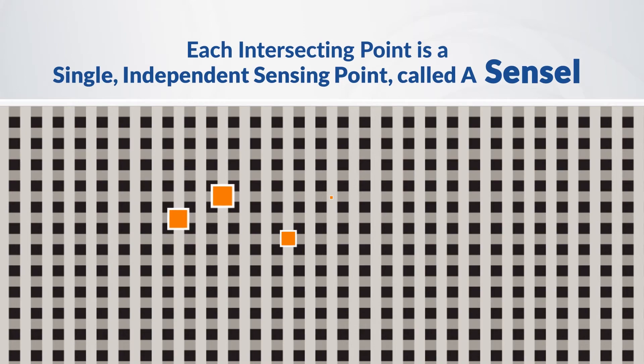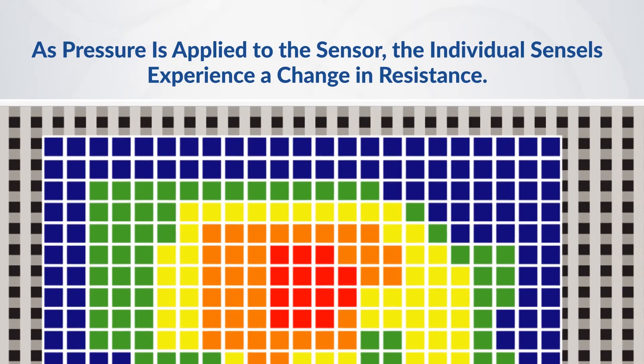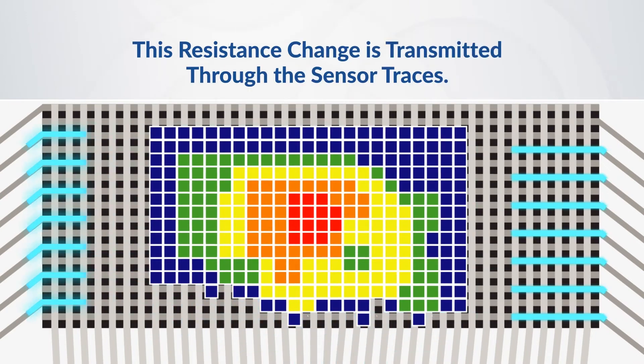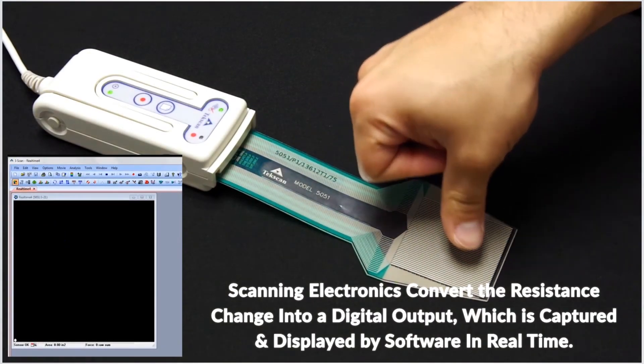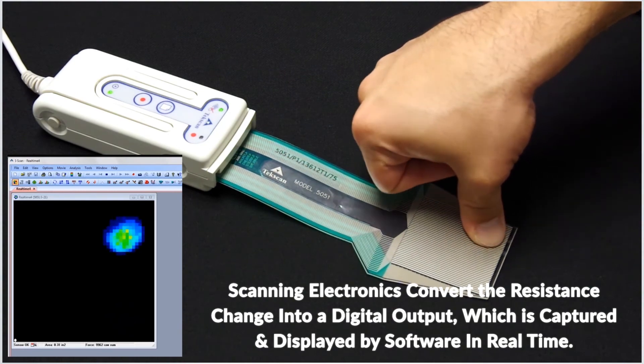Each intersection is a single, independent sensing point called a sensel. As pressure is applied to the sensor, the individual sense cells experience a change in resistance. This resistance change is transmitted down the sensor traces and to the scanning electronics, which convert the resistance change into a digital output, captured and displayed by the software in real-time.